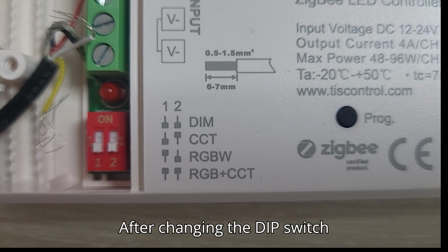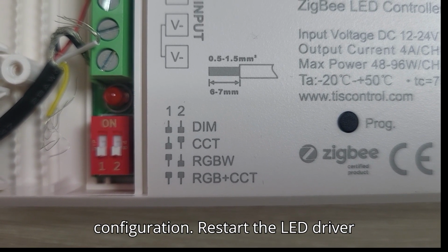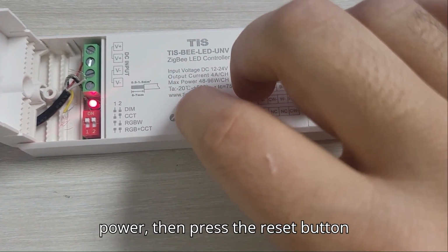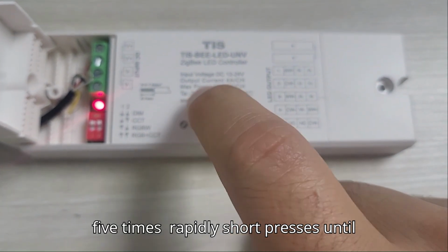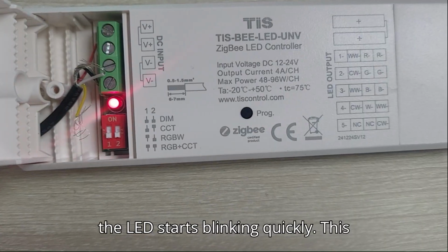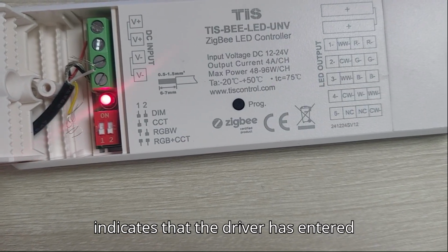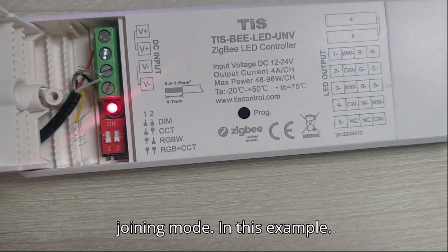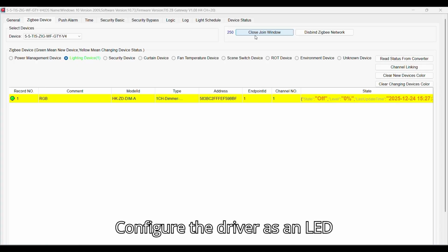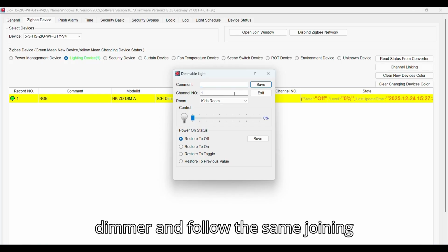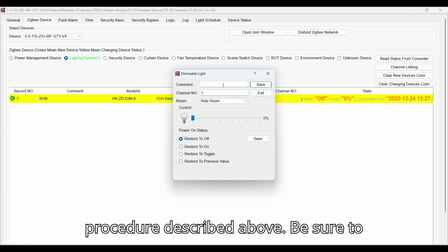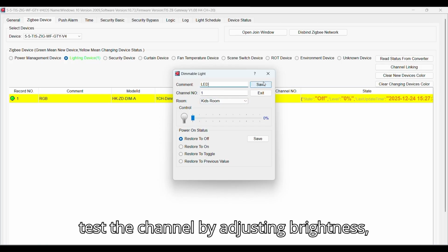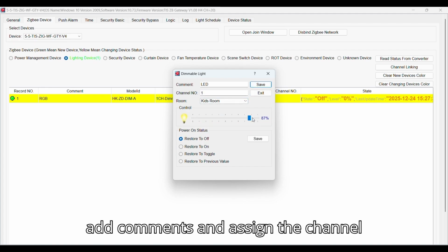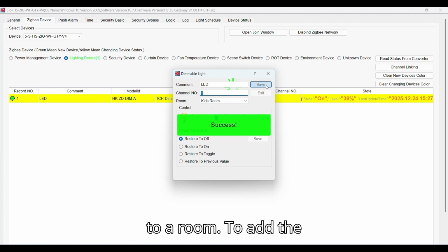After changing the dip switch configuration, restart the LED driver power. Then press the reset button 5 times rapidly, short presses, until the LED starts blinking quickly. This indicates that the driver has entered joining mode. In this example, configure the driver as an LED dimmer and follow the same joining procedure described above. Be sure to test the channel by adjusting brightness, add comments, and assign the channel to a room.